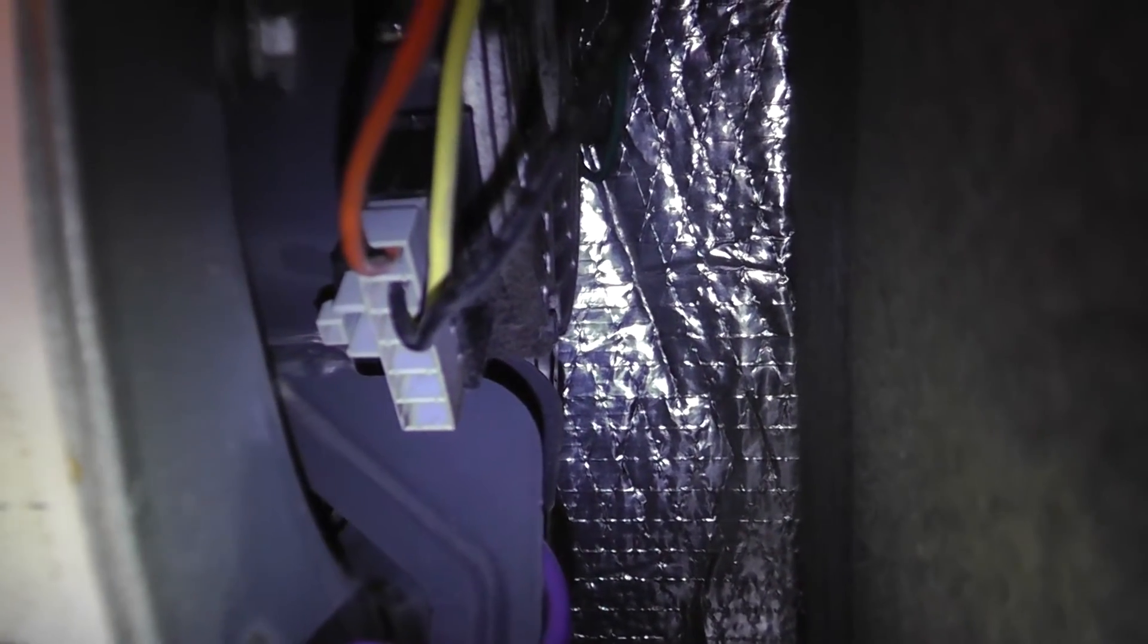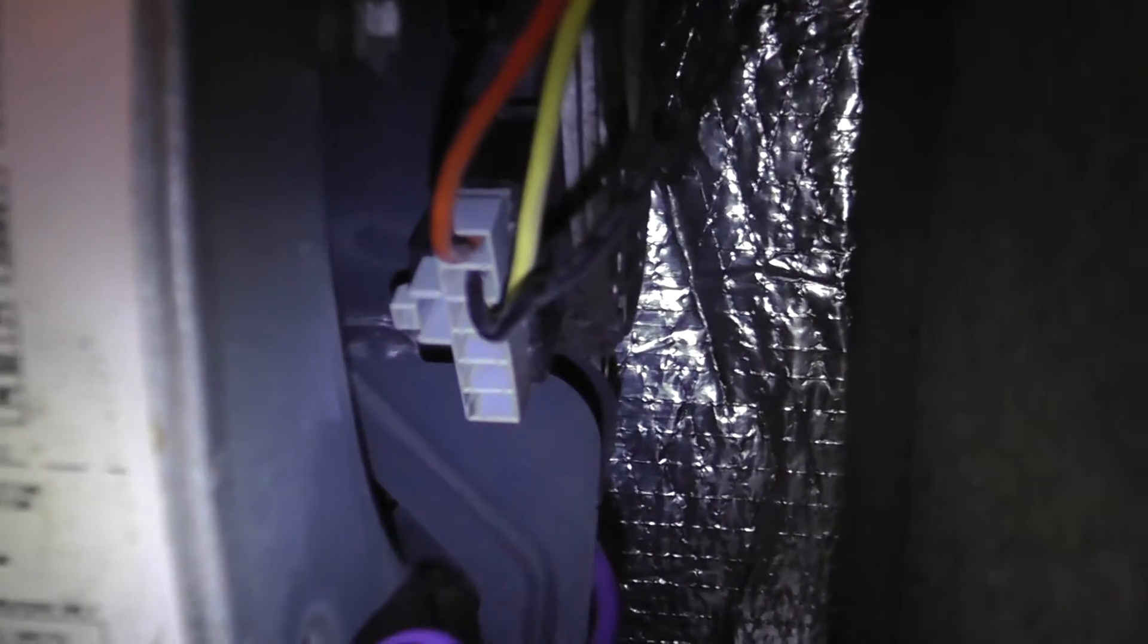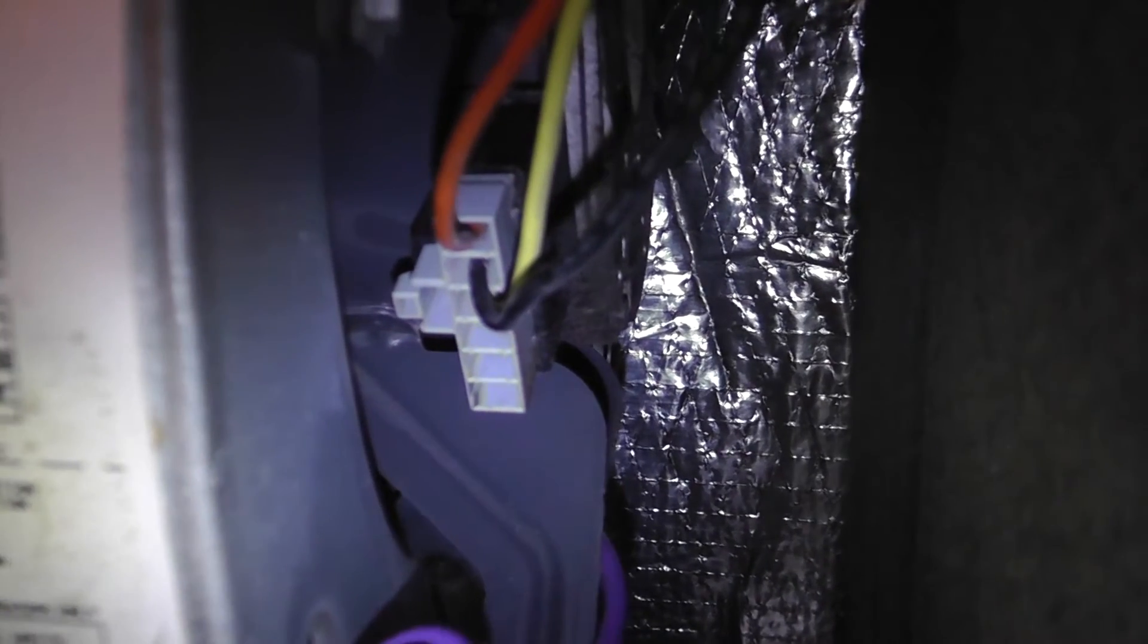We come around to the side over here. Of course, now the light's going to kick on. We've got an orange and we've got a black wire. Let's pull those two leads real quick and we can take a voltage reading right there. What we're going to do is pull those off, put a meter up to it on those two leads, and we're going to ask for a demand for cool at the thermostat. Or actually, we already have it on the thermostat. We're going to plug back in our disconnect and take a meter reading.